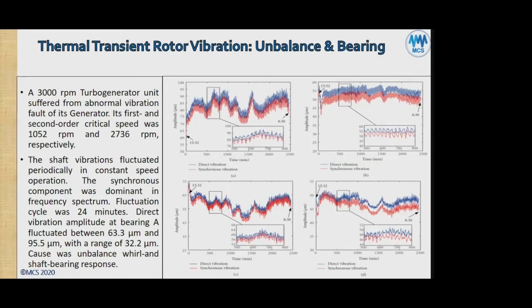So the 3000 RPM generator suffered from abnormal vibration. Its first and second order critical speeds were 1052 RPM and 2736 RPM, respectively. Now, the 2736 might sound not good, but it's still 10% away from your 3000 RPM rated speed. So there would be no sensitivity to the second critical there, unless you're going through rundown as you slow down again, or ramping up. So I'm excluding the shaft vibration as a possibility for this fluctuation. It's too far from the rated speed.